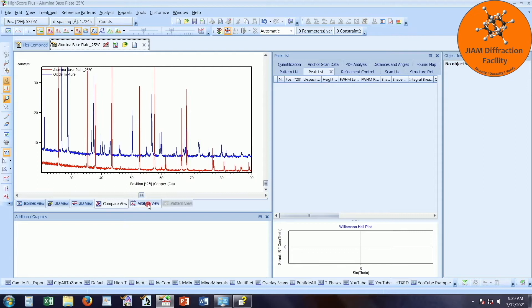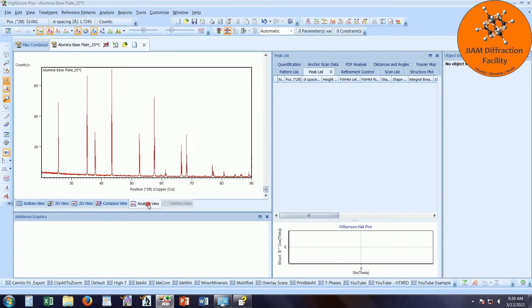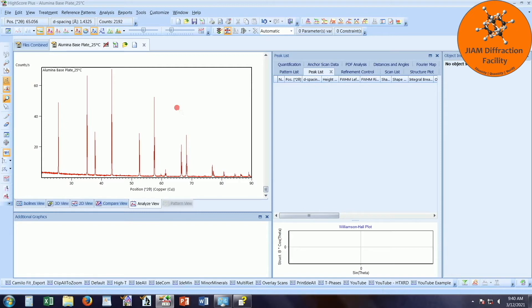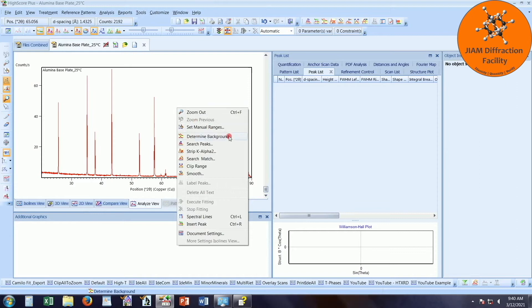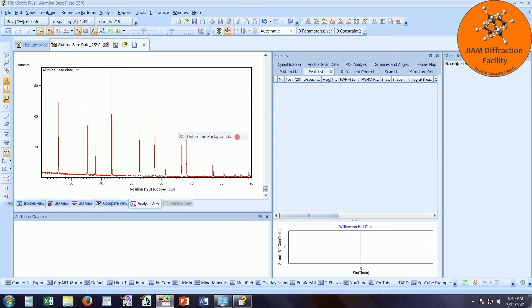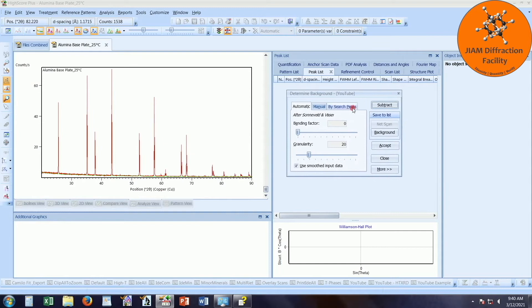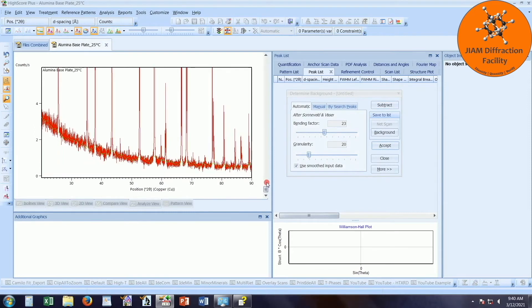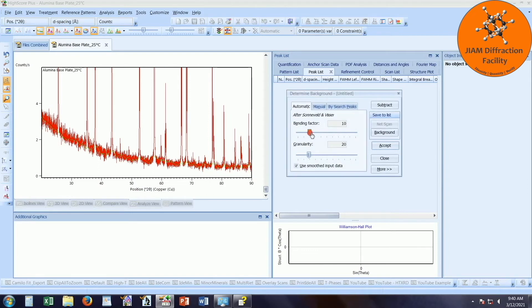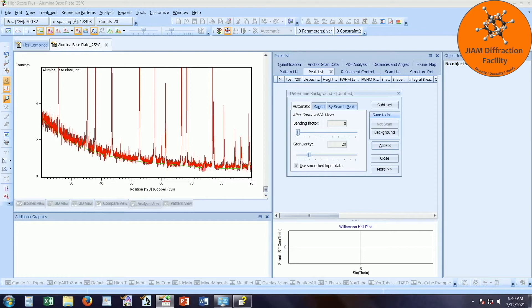Now we see both data sets here. Let's switch again to analyze view, and now I will begin by determining the background. I'm not going to go over all of these steps in great detail. If you want more detail on them, you can view our phase identification video. I'm just going to go over things quickly to save a bit of time and keep this video a little shorter. I will right click, determine background. Now if you have some sort of background set, you can zoom in, see if it looks good. This would probably work fine, but if I wanted to improve it, I could try changing the bending factor or the granularity. A bending factor of zero looks pretty good to me for this pattern. It's not great at the end, but it's okay.